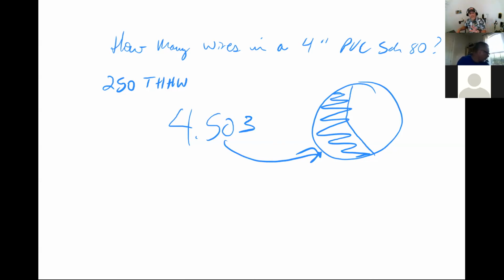Table 5 gives me that breakdown of all the insulated wire by insulation type. THHW is kind of funky because it seems to move around. You'll see it on page 684 on the left-hand side toward the bottom, THHW, but only up to a certain size, then it stops and vanishes. But it picks back up on page 685.